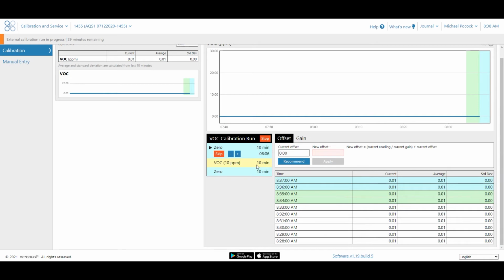So you might not have time or have a requirement to do this really extended calibration for 10 minutes. If you're getting a stable reading after 3 or 4 minutes here, then you might elect to continue on to the next stage. I'd be happy if I'm seeing the exact same reading for say 3 or 4 minutes that the module is stable. If I was doing this in a laboratory, or I was doing it for the first time, I really would want to do the full 10 minutes just to ensure that the monitor is stable. But in the field, you might not always have time to do that. So 3 or 4 minutes of a stable number would generally mean you'd be fairly sure that you have a valid reading. So the next thing to do would be to skip to the next section because you're happy with this number.